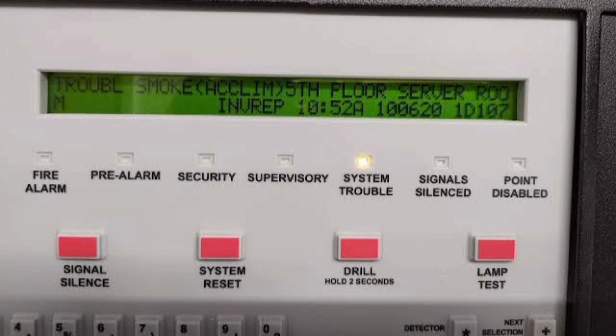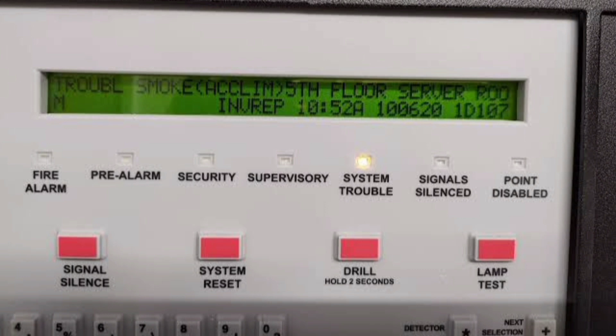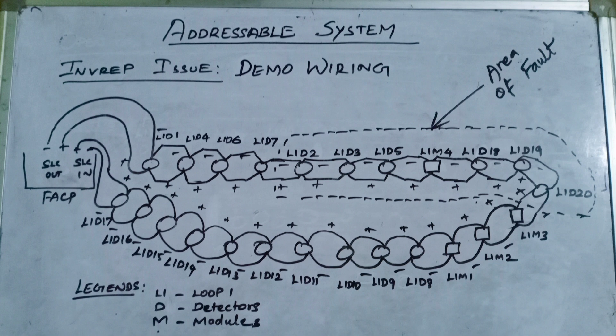Now let's get into troubleshooting of invalid response. When we get troubles on the display of the panel — some of my colleagues pronounce this like 'in-verb' — ha, it's a joke. This is based on my experience from the NFS 320 and FireLite MS-9600LS panels. Invalid response means there is no communication between the devices and the panel PCB. Because of this lack of communication, the device will disappear from the panel unless you take action.